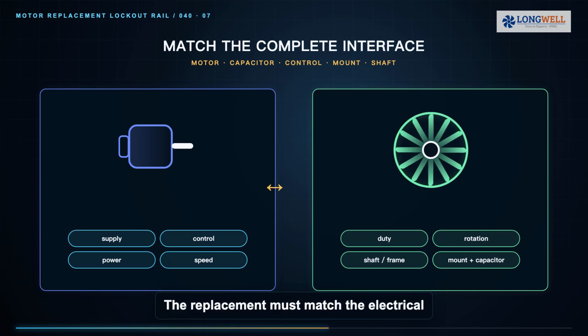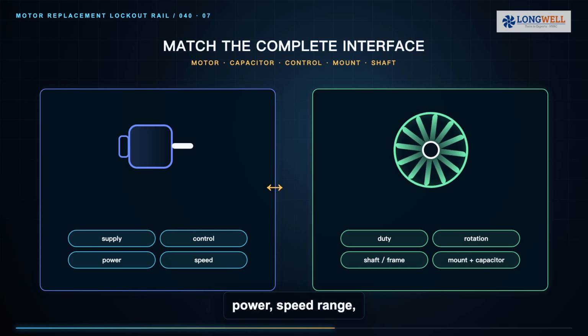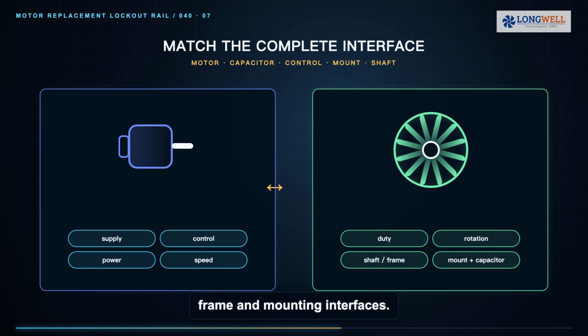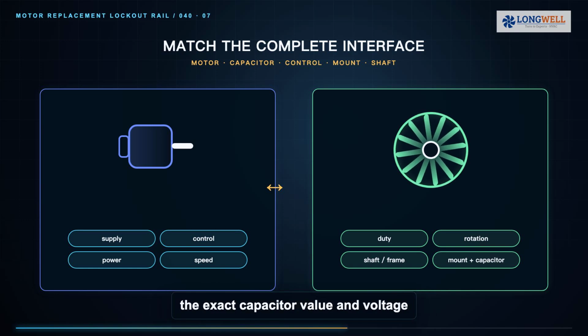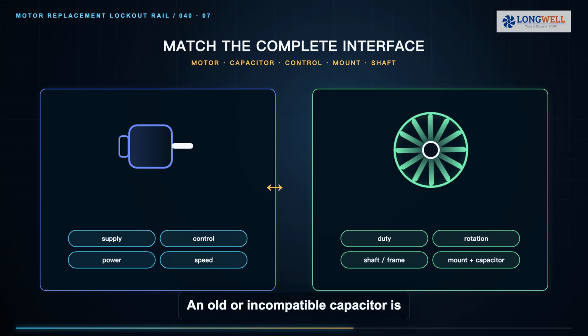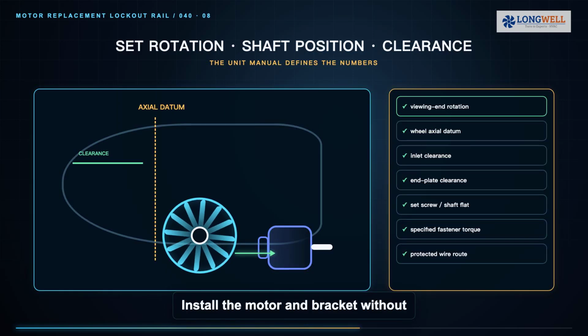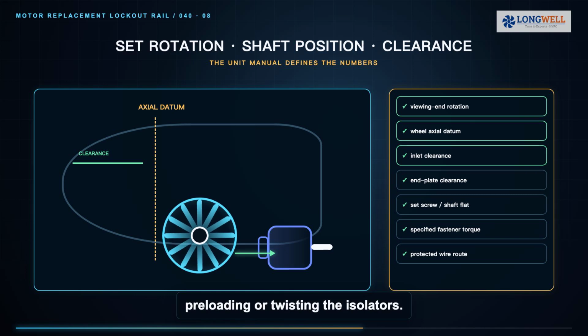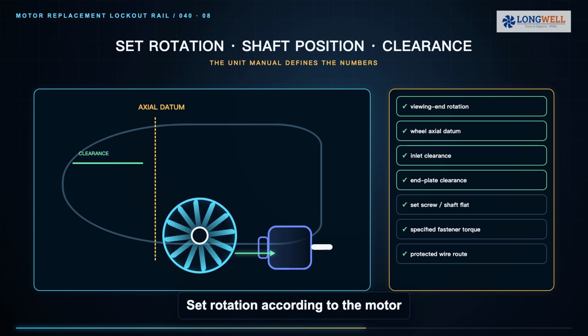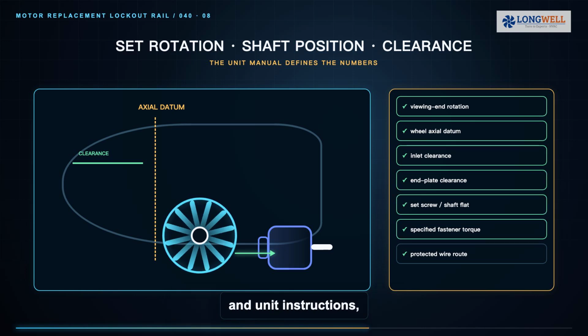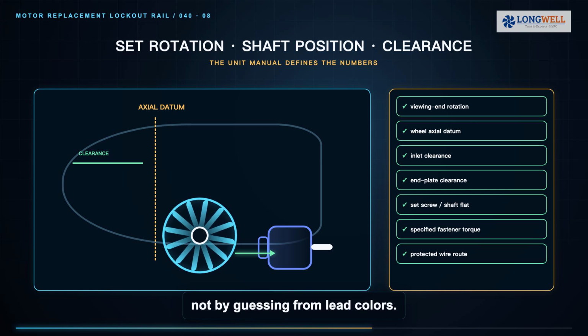The replacement must match the electrical supply, control method, power, speed range, duty, rotation capability, thermal protection, shaft, frame, and mounting interfaces. A capacitor-run replacement also needs the exact capacitor value and voltage class specified for that motor. An old or incompatible capacitor is not a harmless shortcut. Install the motor and bracket without preloading or twisting the isolators. Set rotation according to the motor and unit instructions, not by guessing from lead colors.